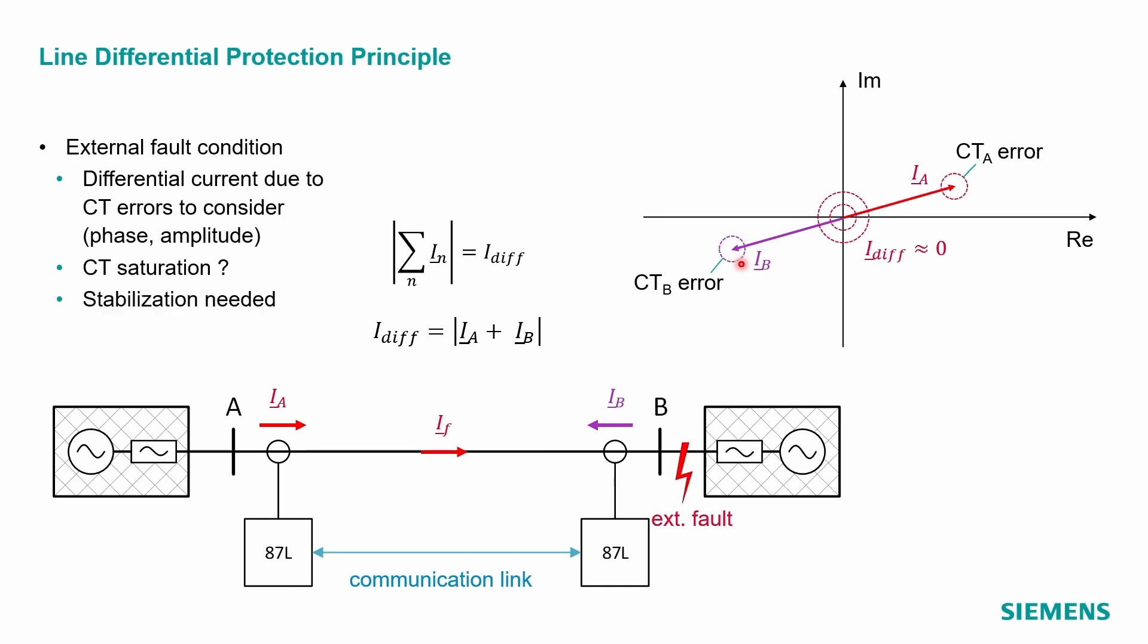This is particularly the case if you have an external fault situation. The measured currents at the line terminals are the through fault currents. The higher currents result in bigger CT errors and therefore a higher differential current. For this reason, we need a minimal pickup threshold for the differential current setting. In extreme situation, one CT could saturate and the apparent differential becomes very big. For this, we need other types of stabilization, which I will present later to you.